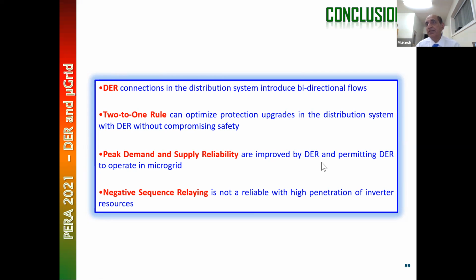Now, distributed resources can shape the peak, basically deferring the cost of capital investment for capacity reasons. They can also improve reliability by permitting DR to operate in a microgrid. And high penetration of inverters can compromise negative sequence protection relays. That's a big challenge our industry is facing, for which, again, I did not talk about grid codes. New grid codes are being introduced, forcing IBRs, inverter sources, to supply negative sequence current so that reliable protection decisions can be made.